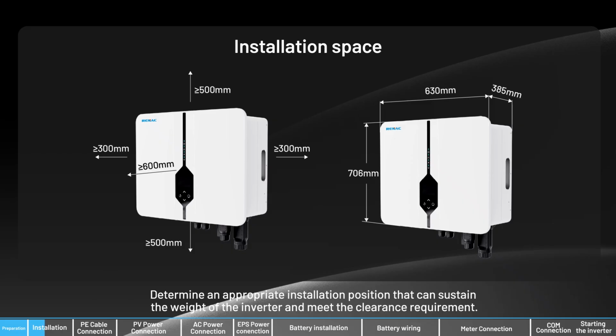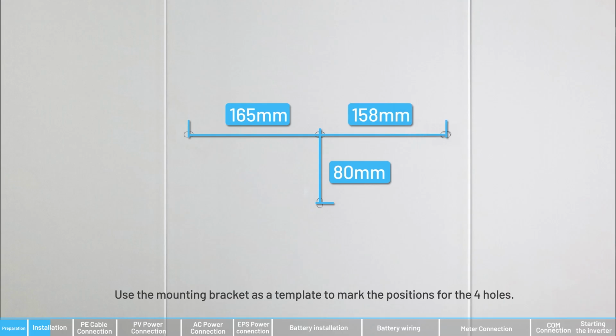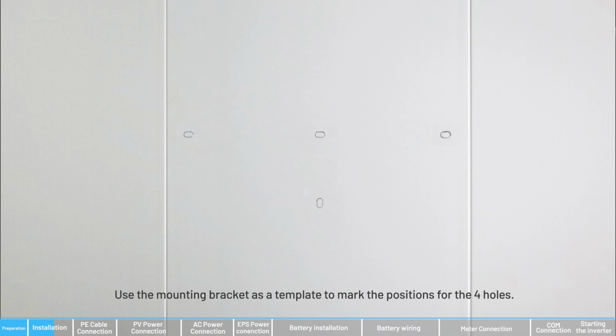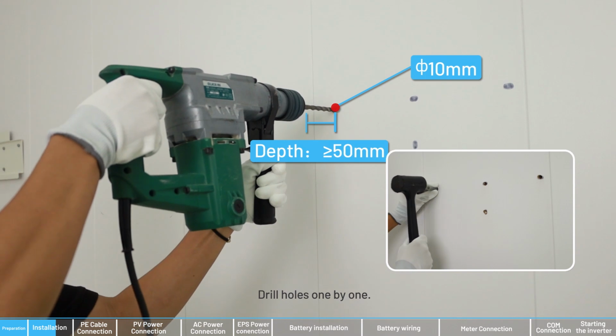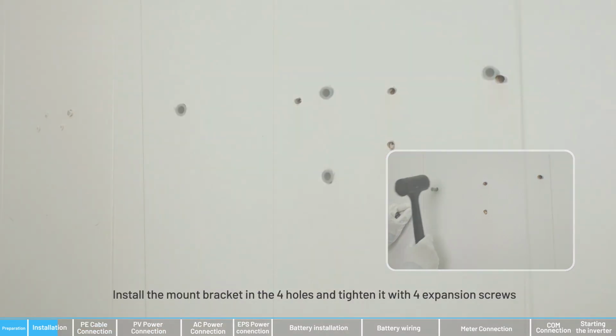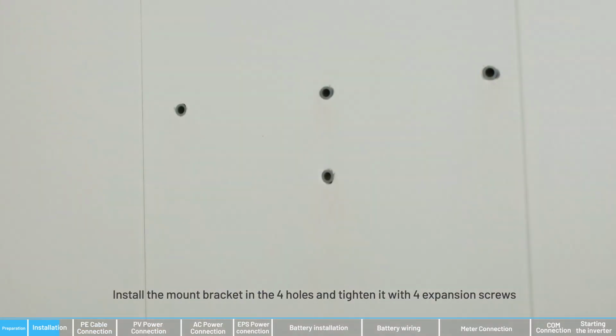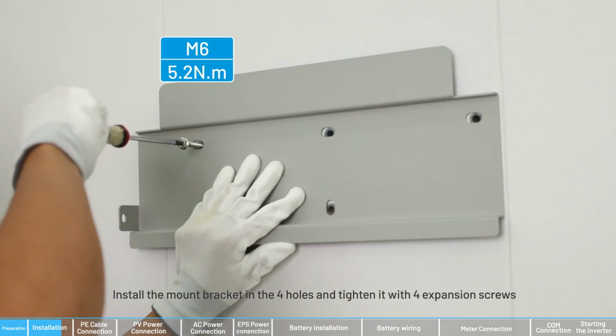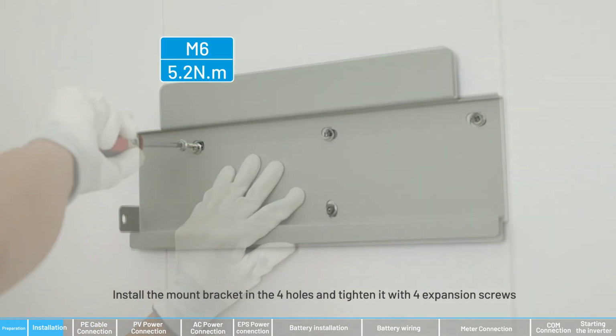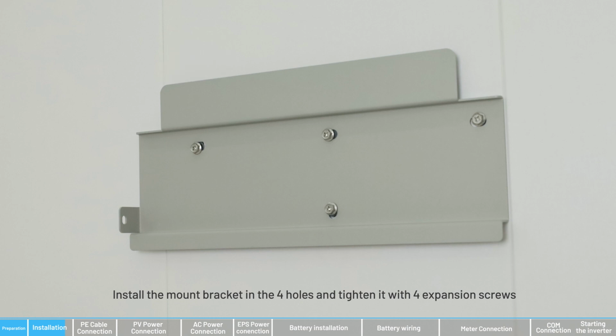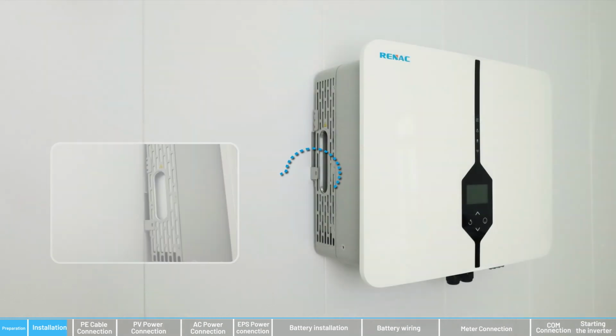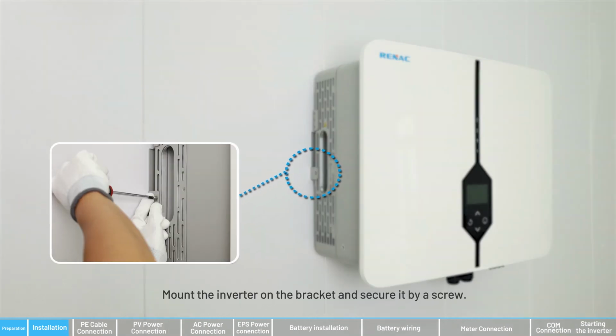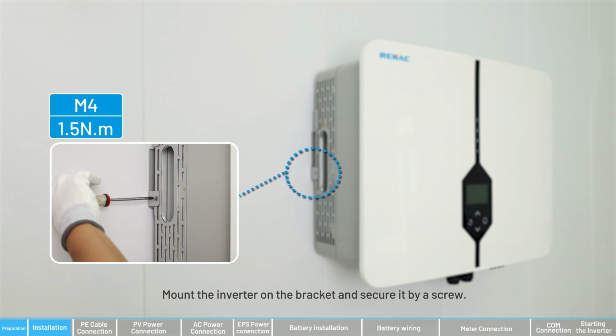Determine an appropriate installation position that can sustain the weight of the inverter and meet the space requirement. Use the mounting bracket as a template to mark the positions for the 4 holes. Drill holes one by one. Install the mount bracket in the 4 holes and tighten it with 4 expansion screws. Mount the inverter on the bracket and secure it by a screw.